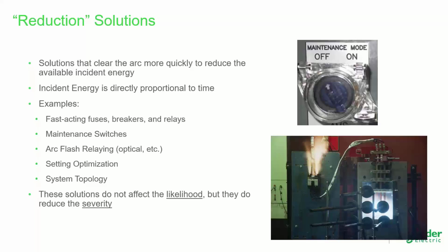If you change your clearing time from 1 second to half a second, for example, you reduce the available incident energy that could result from a fault at that location in the system. You cut it in half. Simple enough. And so if we can use fast-acting circuit breakers, if we can use fast-acting relays, fuses, whatever it may be, we can help reduce those energy levels. Arc flash maintenance switches may help us reduce the clearing time and reduce the energy when we might have problems otherwise maintaining coordination in the system. Optical sensing relays and other innovations are new ways to help detect and clear faults more quickly, but sometimes we don't have to use the new technology to get there.